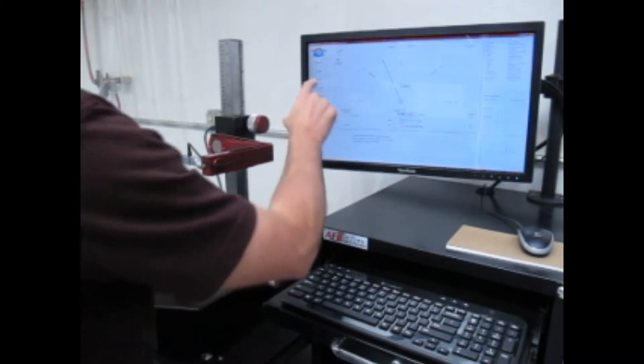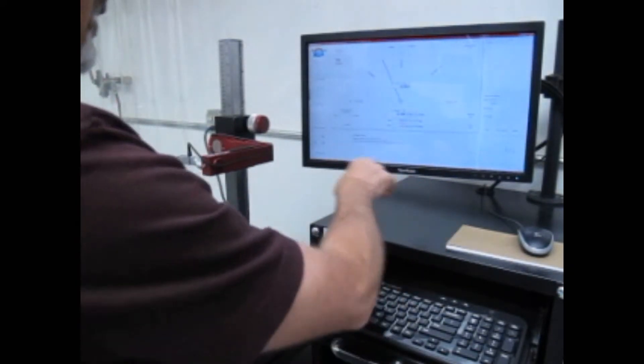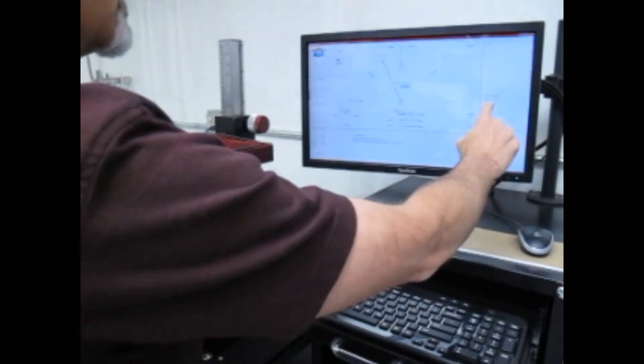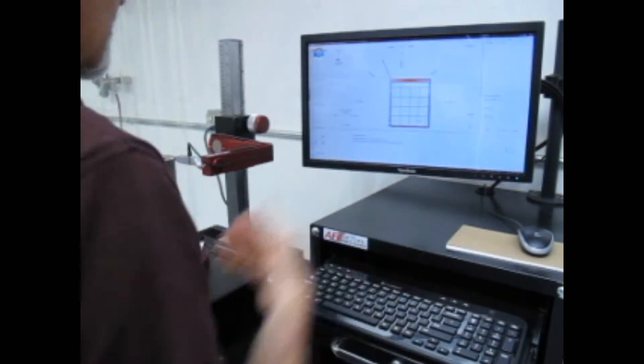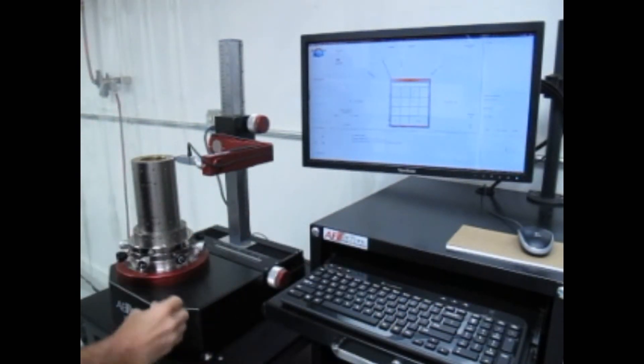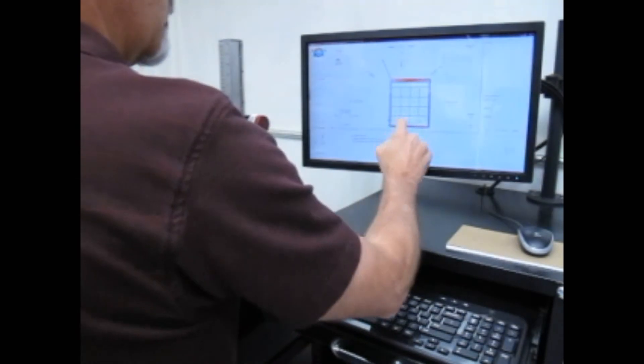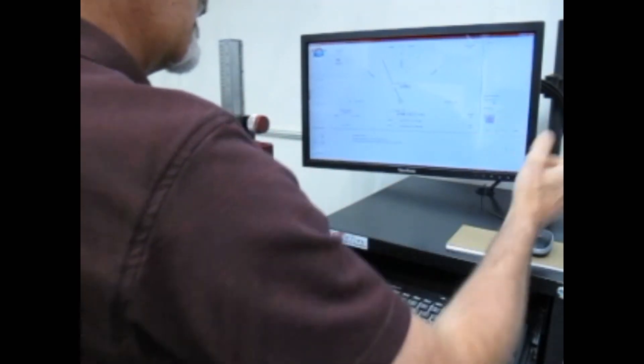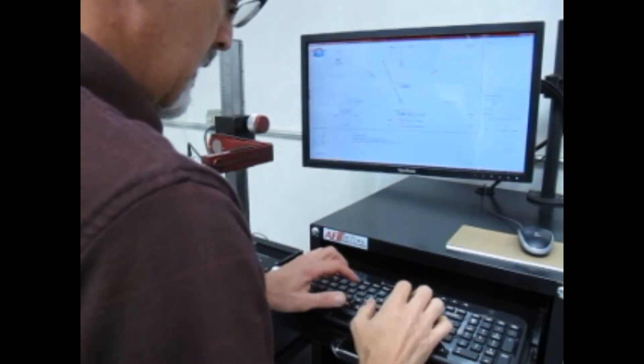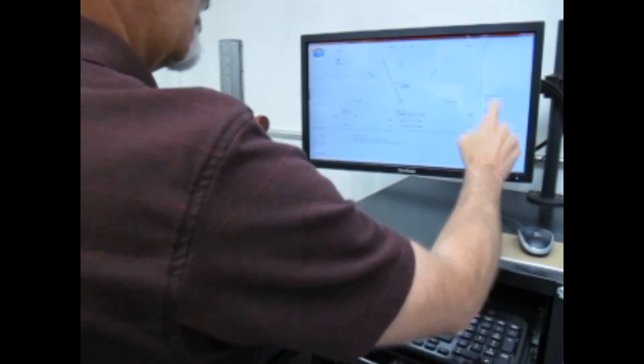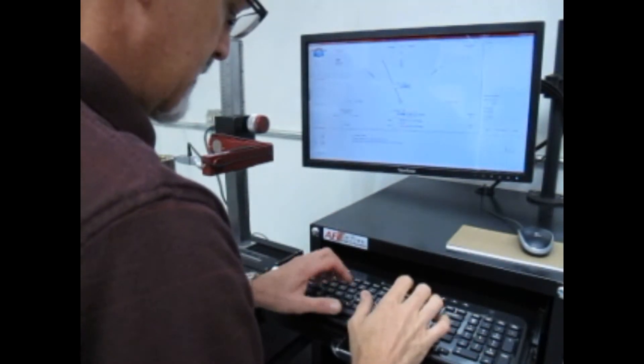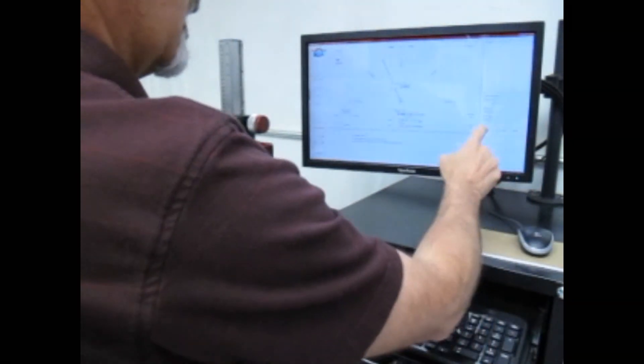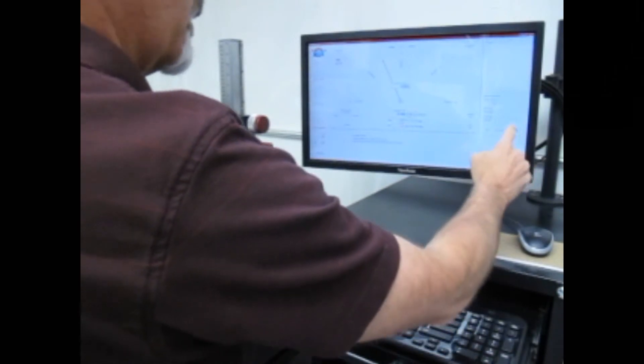So I'm going to select parallelism and it tells me here that I need to put inputs. In this case it asks me for the radius so I'm going to use the scale down here and I'm at 1.625. Enter that. I can put in the part name. Test artifact from before. I can put in a comment. This is the top base.